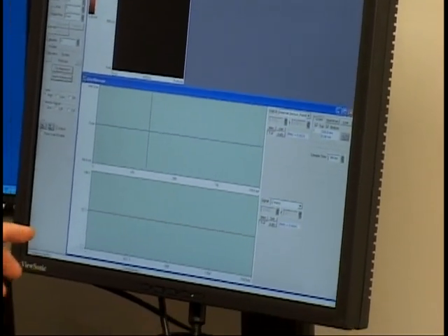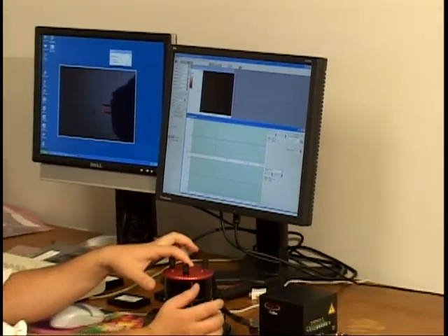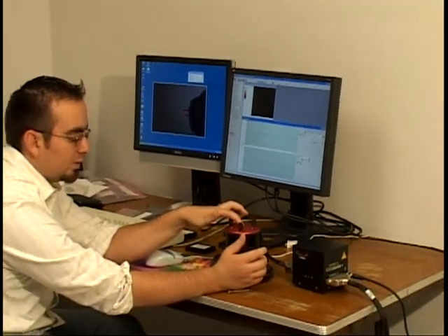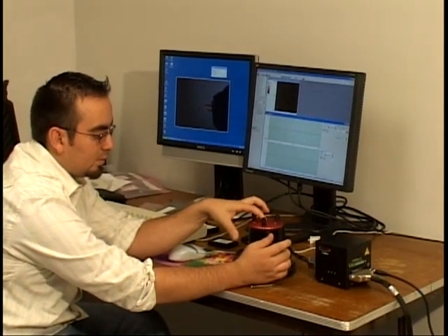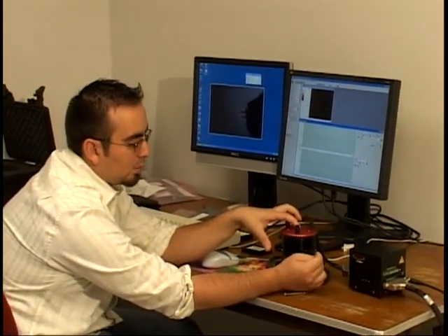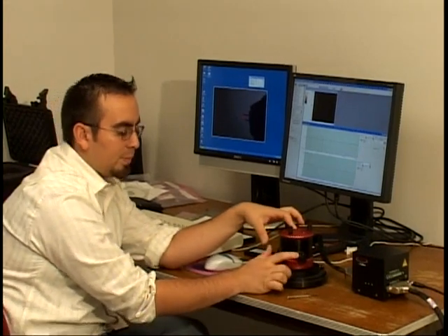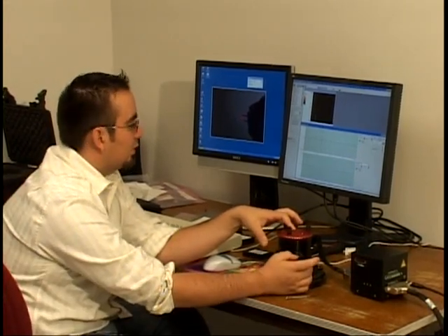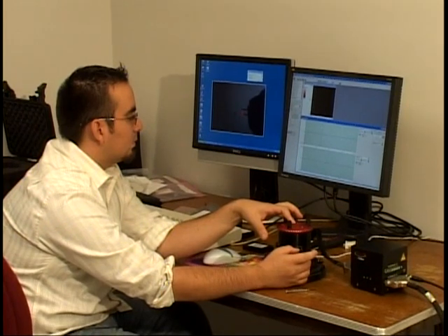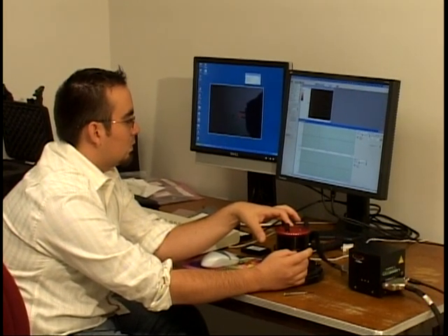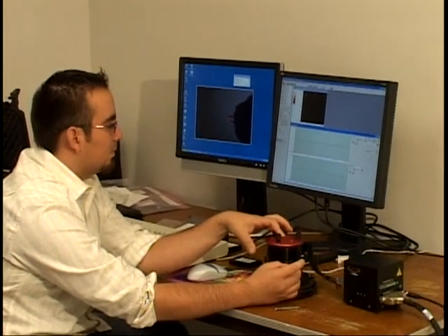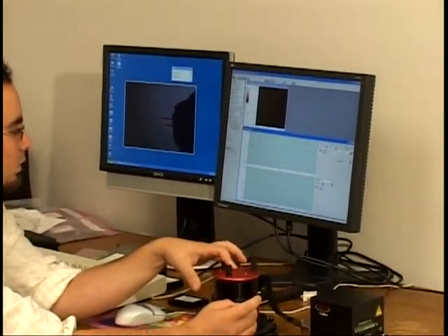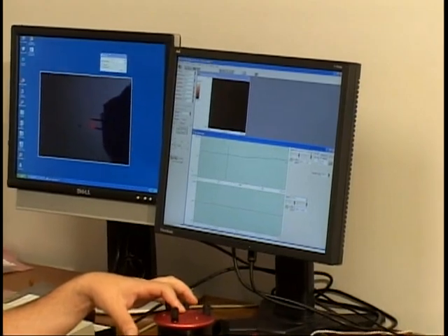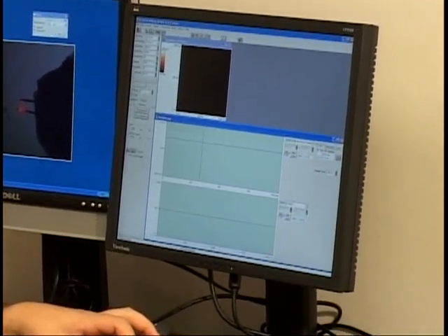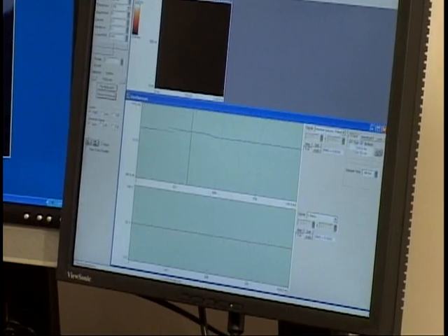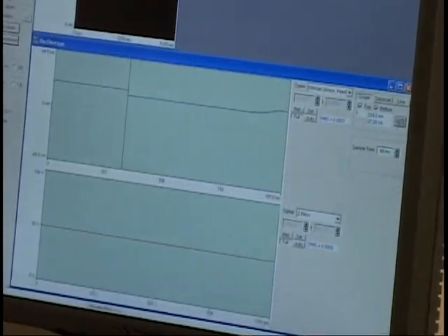So the first thing you do, one thing I usually do, is put my left hand on top of the cantilever head. That way it doesn't move around the stage if we start moving around these knobs. And then move the top bottom knob, which is the bigger knob, and try to adjust that until you see some sort of sum, or where you can actually see a maximum sum. So you'll see it increase, and it'll come back down, so we go back up.